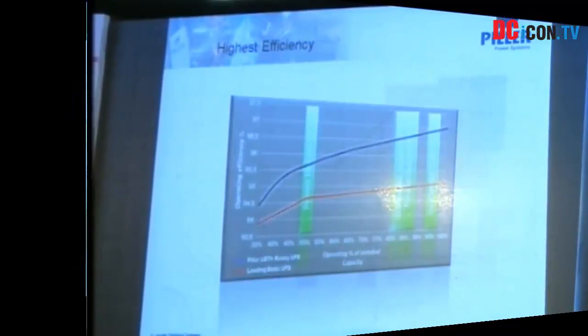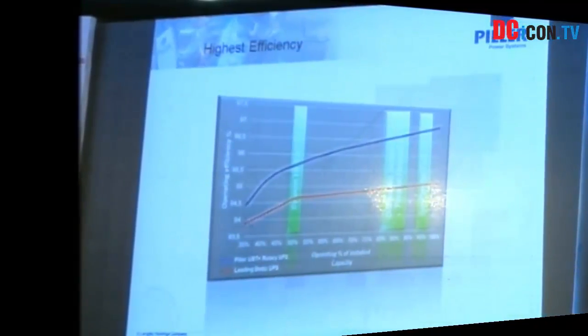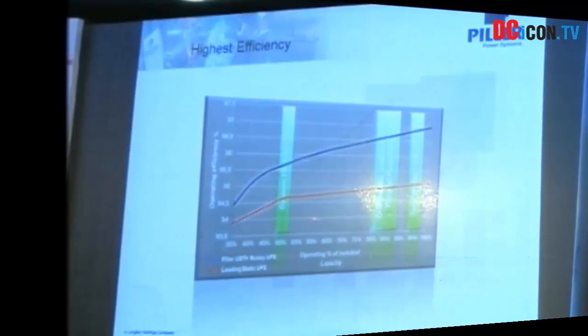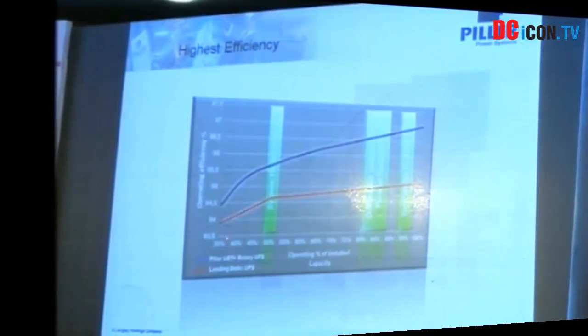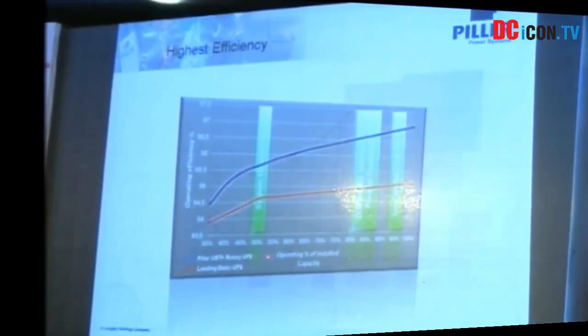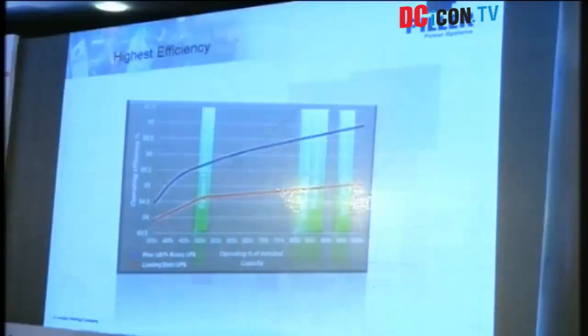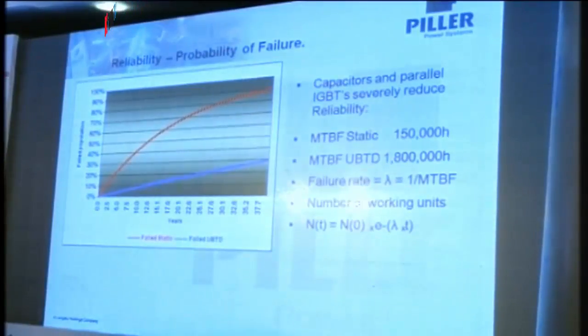Okay. Of course, the efficiencies are high. We've already seen that. And you can see that this is the Piller UBT+ Rotary UPS, whereas this is a leading static UPS, and these are the efficiencies. At 50%, also you have a very high efficiency. Most of the data centers operate at 40 to 50% load. So even with that particular load, the efficiencies are very high. And as you approach a higher load factor, the efficiencies are much better than static UPS.